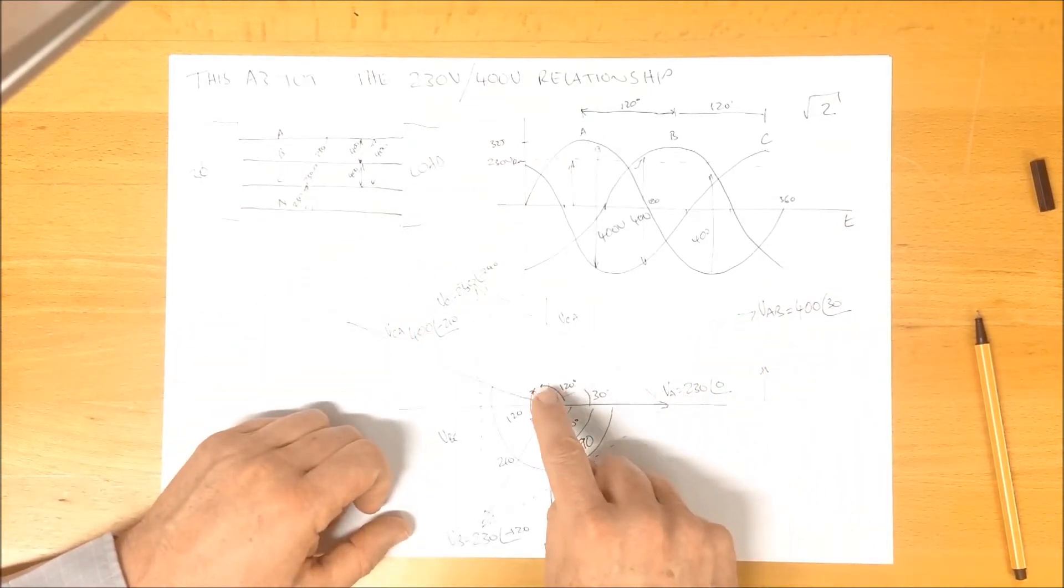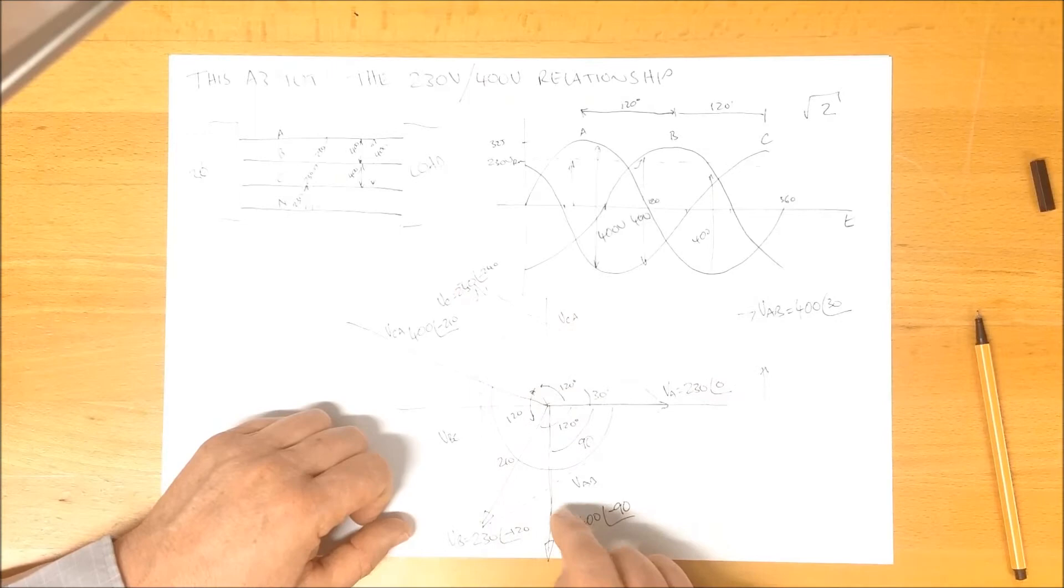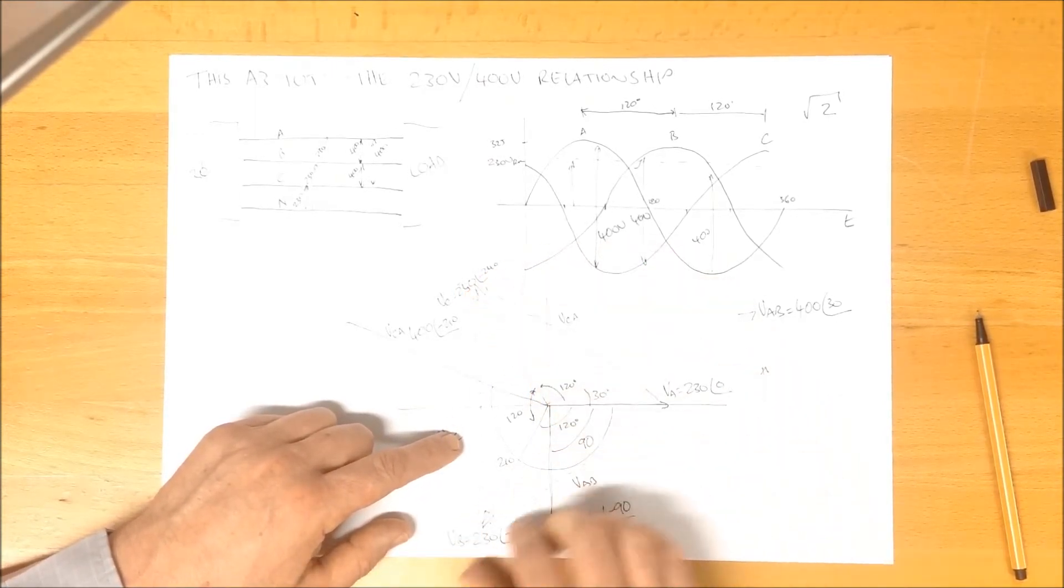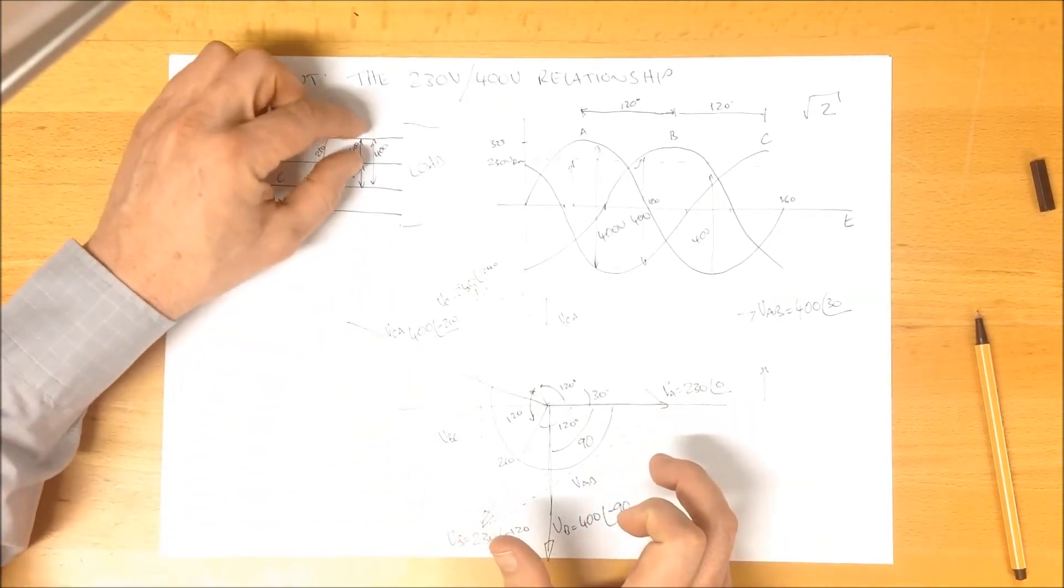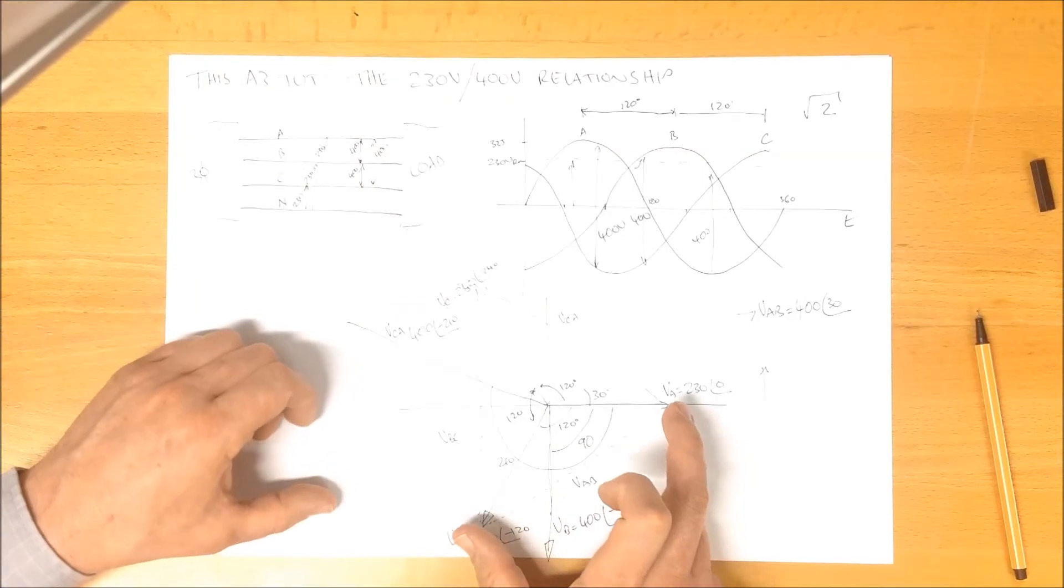We've got our phase voltages, which everyone knows about, our 230 at zero, 230 at minus 120, and 230 at minus 240. And then we've measured between those two, just as we would up here, between here, and we see there are 400. We reference that to our origin.